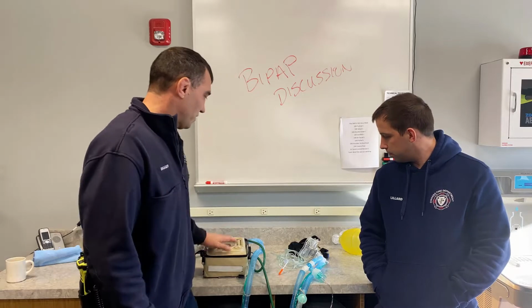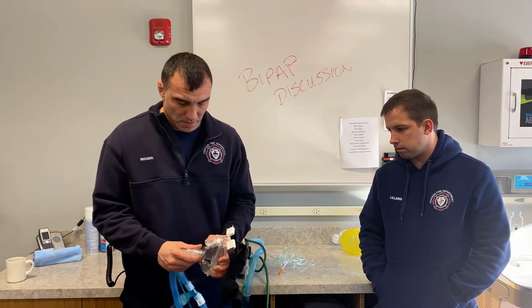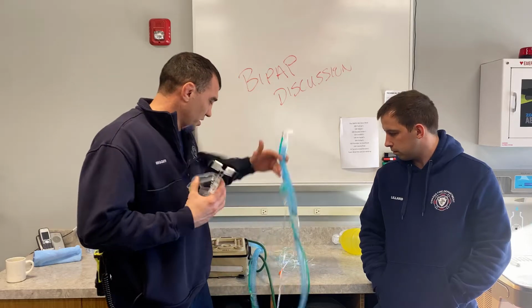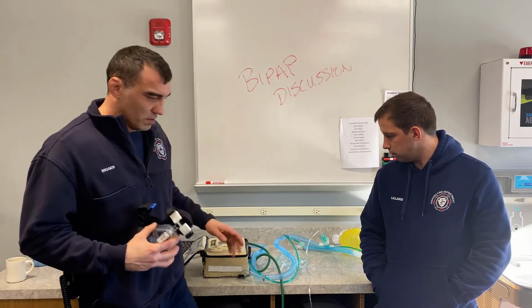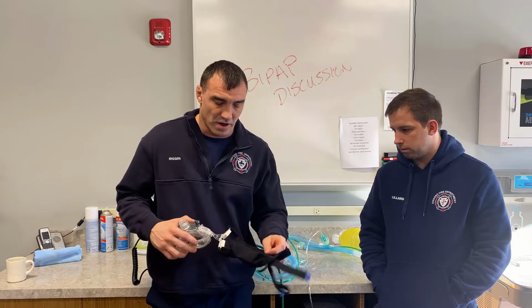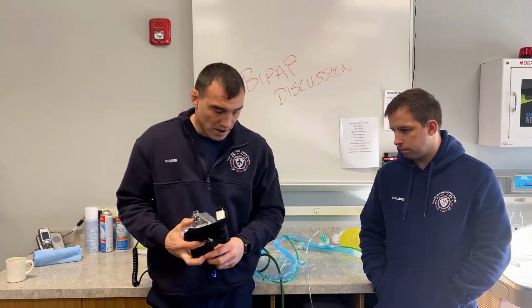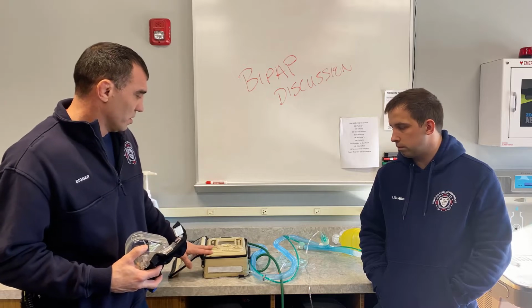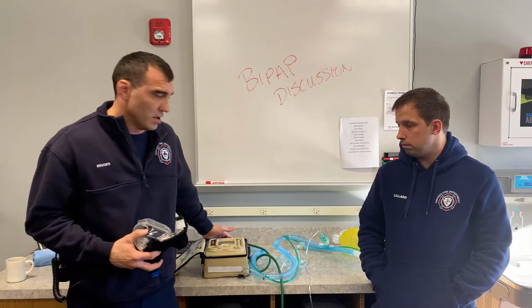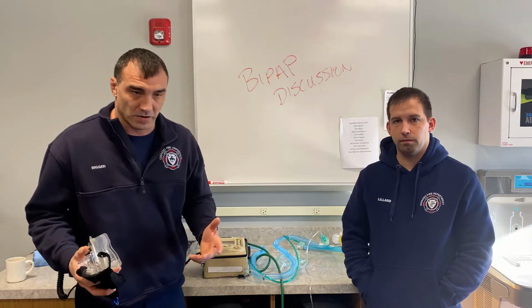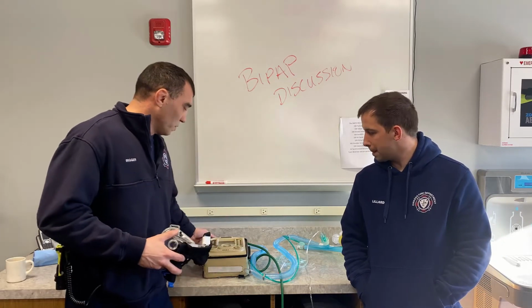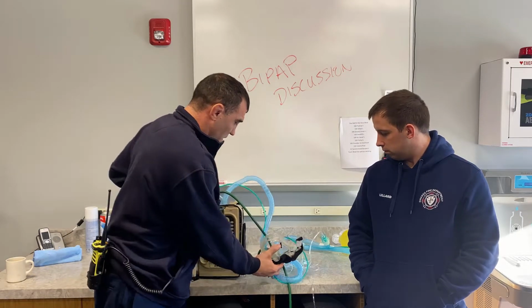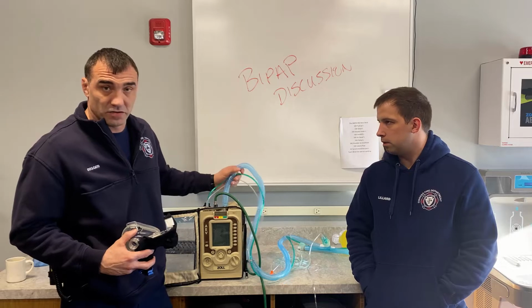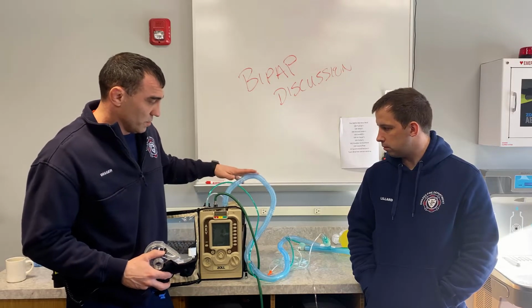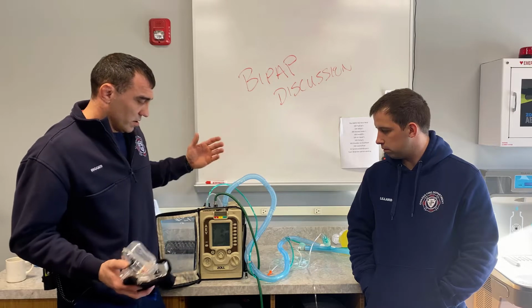All right, guys. So Pat just went over how to set it up. It's a pretty simple setup on the BiPAP. The biggest complaint or issue that we get is the vent alarming for patient disconnect, or it's detecting that you have a leak. I had one the other day, and they said, well, we have a patient disconnect alarm, but I've checked all my connections, they are correct, and the mask is on, so we don't have a patient disconnect. But you're wrong, you still do. What that's telling you is that it's detecting a leak. All it knows is it's not getting the resistance that it thinks it should, according to its calibration, through the ventilator. So that's exactly how you troubleshoot it.